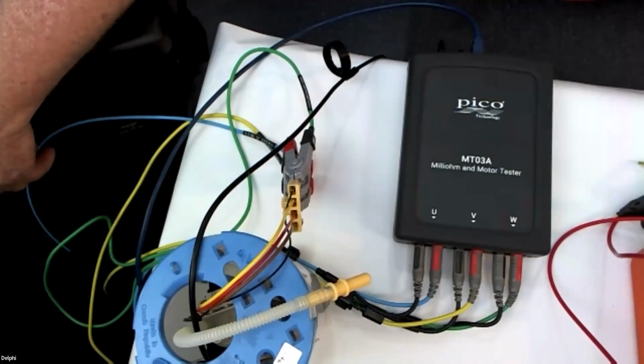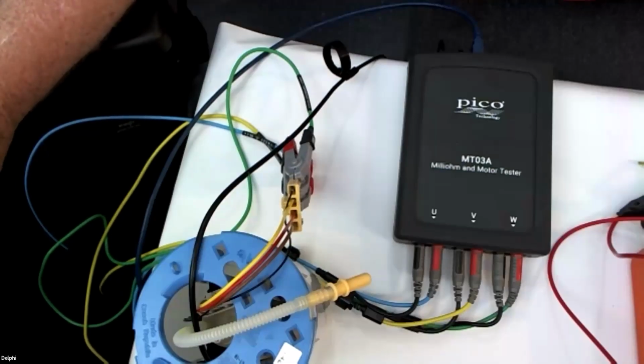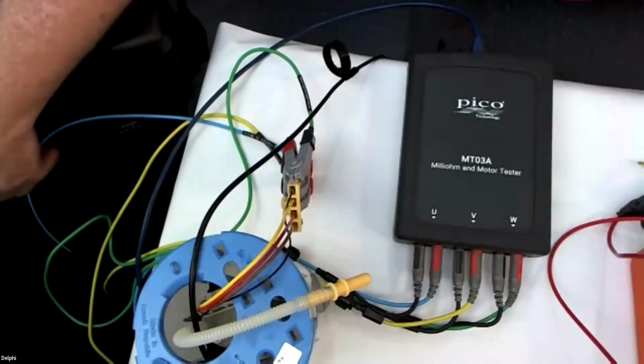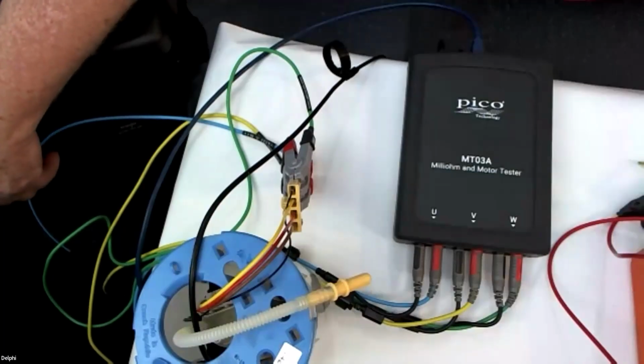It's checking between U and V, and you'll see the action going on with the animation. Now it's going to switch over to V and W. It gives the number, 143.82. Hey, didn't we see about 143 or 144 or 141 when we used the little VC, the little expensive tester? Worked the same way. This is just going to be a little self-test, and it gives us a bar graph so you can see trends.